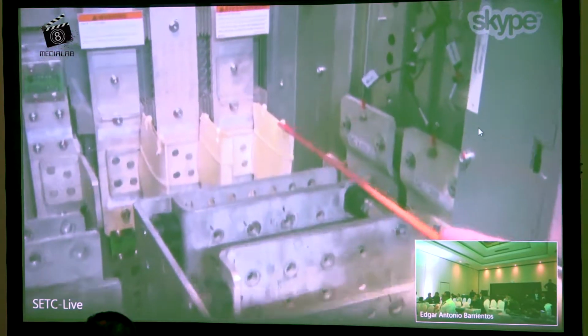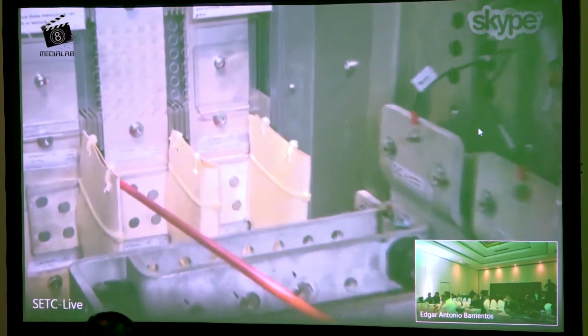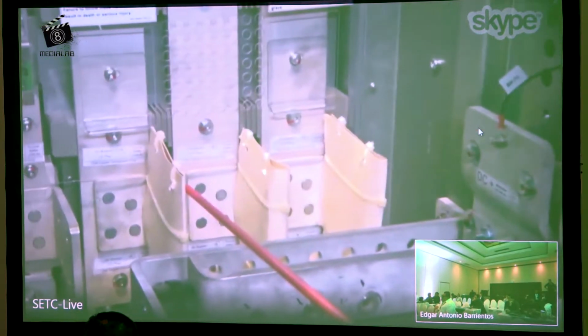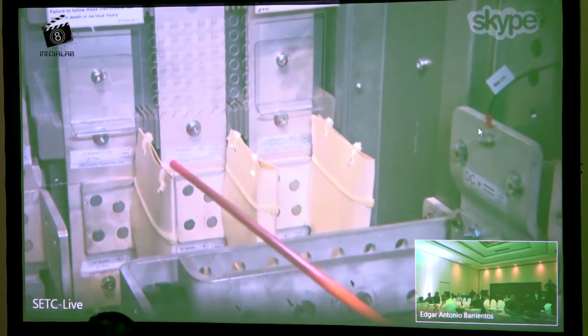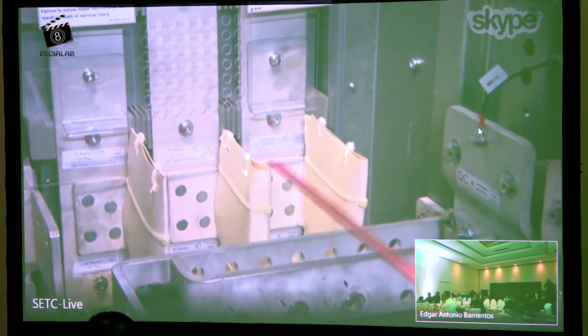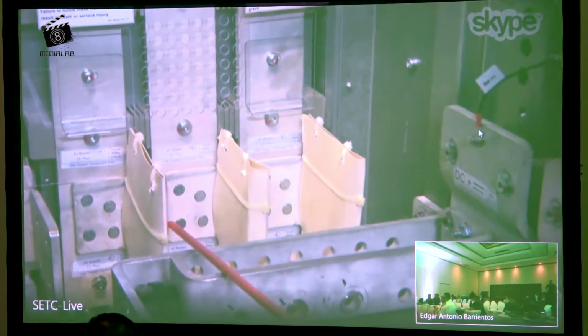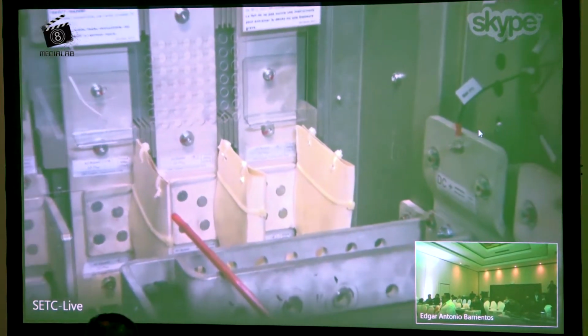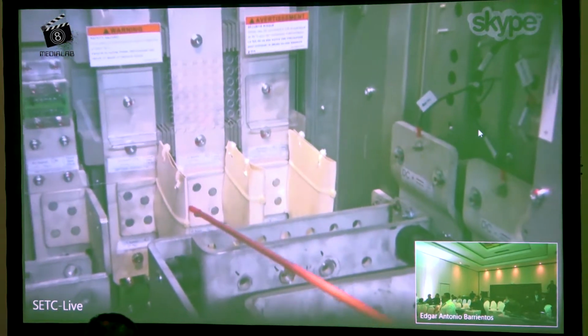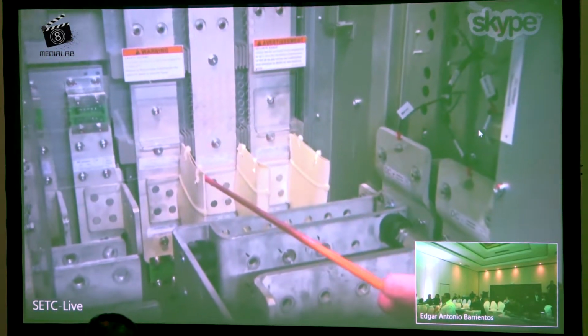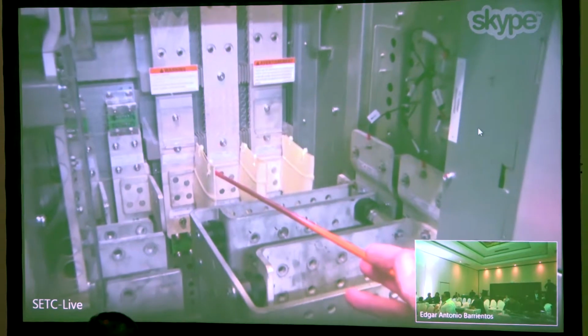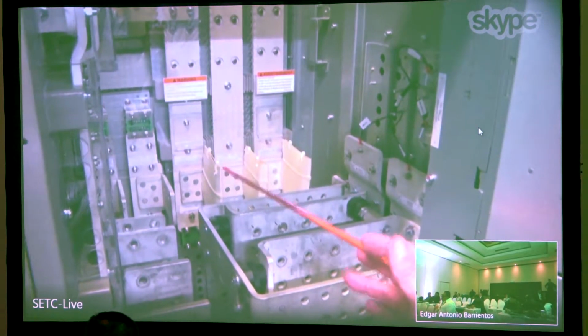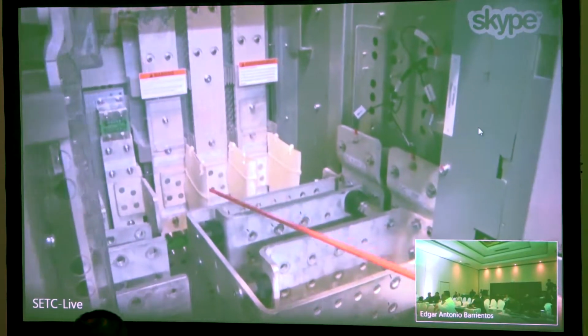Over here in this right rear corner is the input to the static bypass. So if you're going to do dual mains, this would be the input to the static bypass, and we'll show you the inverter and rectifier input in just a second. If you're not going to do a double mains, then we have a single mains kit that ties the bus together, and we'll show you that in just a second.